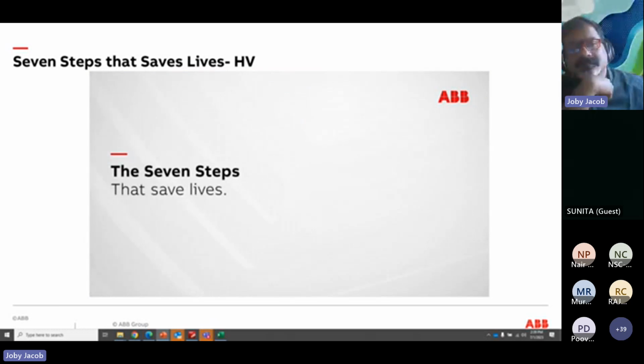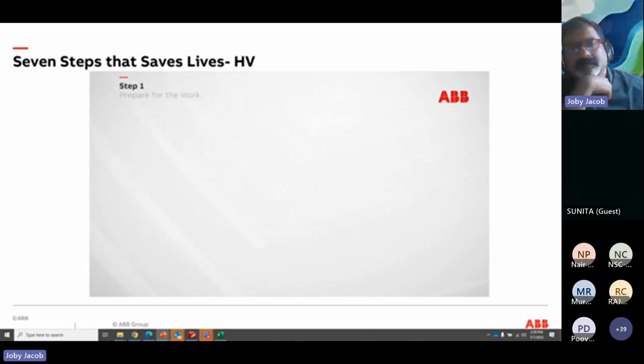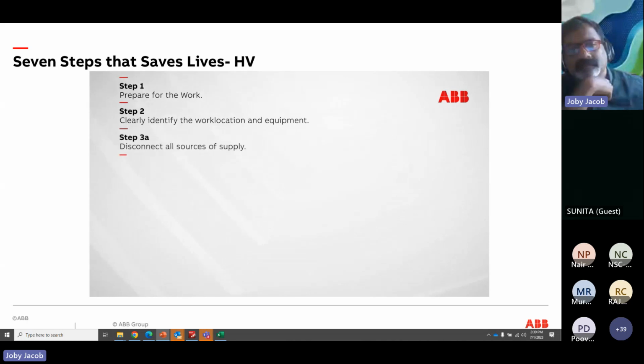Here are the 7 steps once again. Step 1. Prepare for the work. Do an on-site risk assessment or job hazard analysis. Step 2. Clearly identify the work location and equipment. Step 3A. Disconnect all sources of supply. Step 3B. Secure against reconnection by applying lockout-tagout.